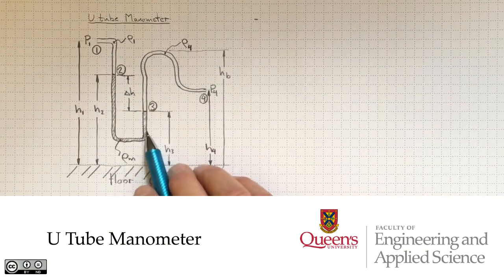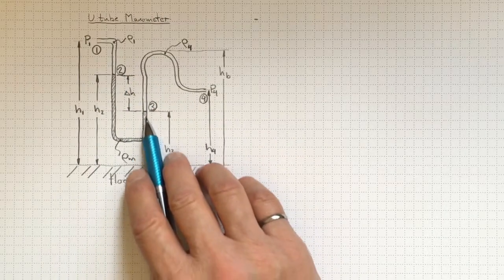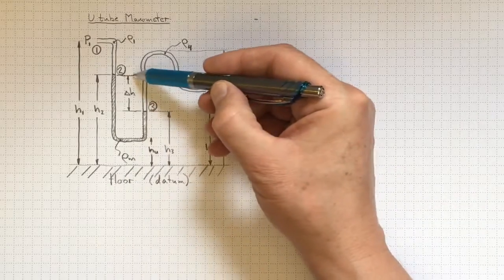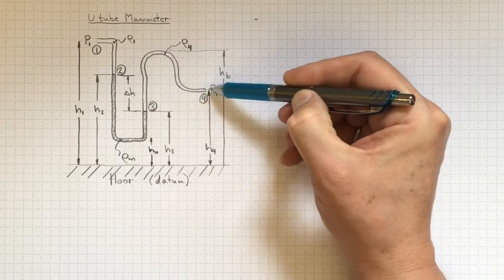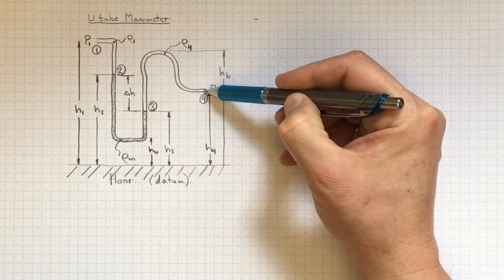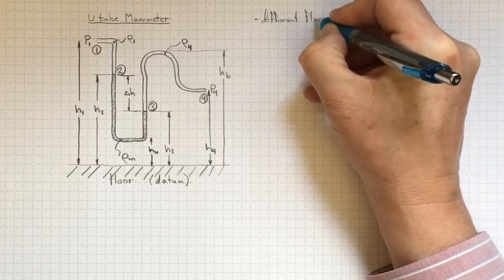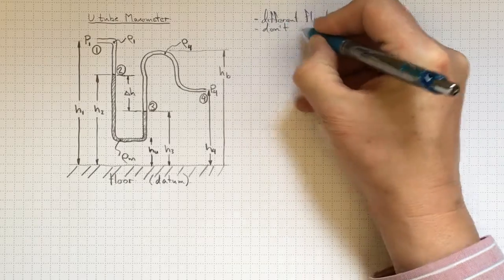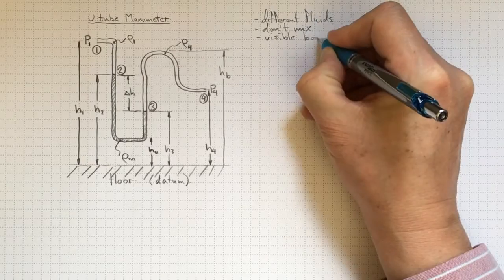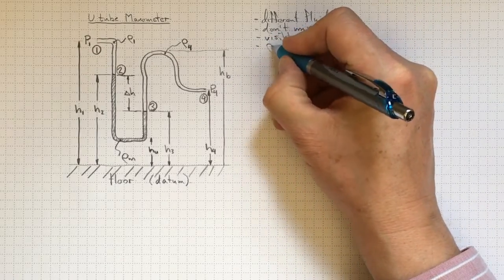A U-tube manometer like this one takes advantage of having two different fluids or more inside tubes and taking advantage of the density differences between those fluids and the difference in elevation that's produced by applying different pressures to either end of the tube to make a pressure measurement. So the key things are that we have different fluids, that they don't mix.